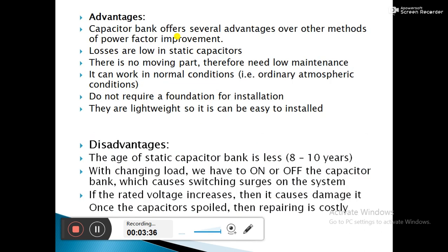The advantages of the static capacitor method are: losses are low; there are no moving parts, therefore low maintenance is required; it can work in normal atmospheric conditions with no special temperature requirement; and it does not require a foundation for installation since the capacitors are light in weight and can be installed anywhere easily.